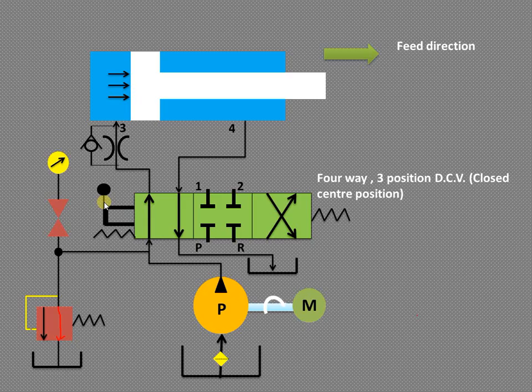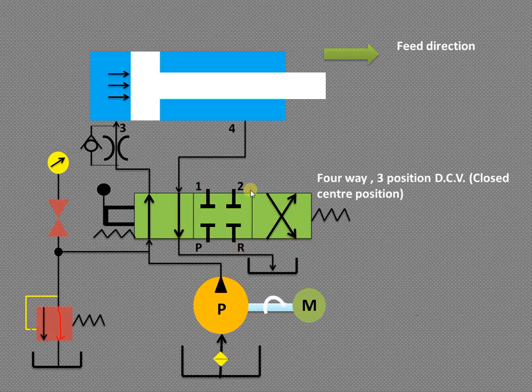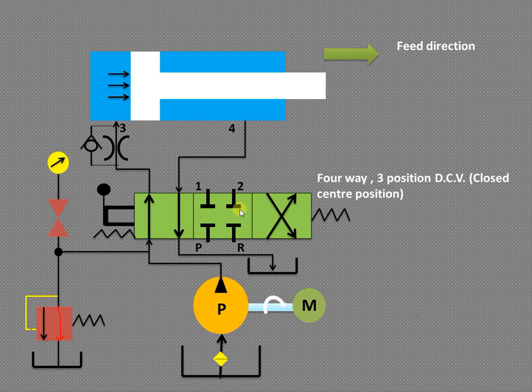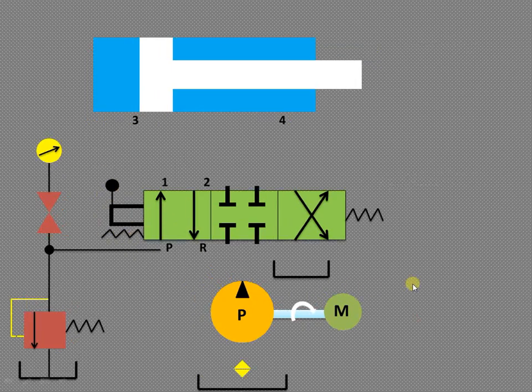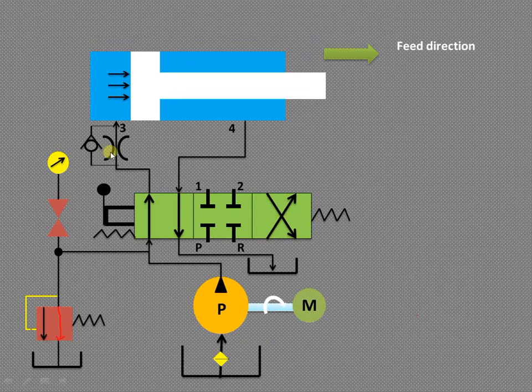From port 2 the fluid goes to R and then back to the reservoir. When we release or operate the lever to get the right envelope mode, P and R and ports 1 and 2 shift accordingly. This is the four-way three-position directional control valve: three positions being the center block position, left envelope mode, and right envelope mode — lever-operated and spring-controlled.